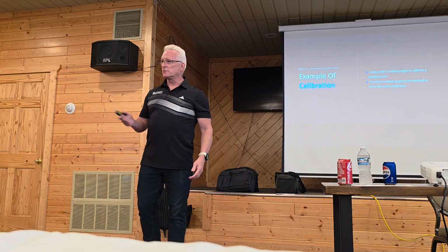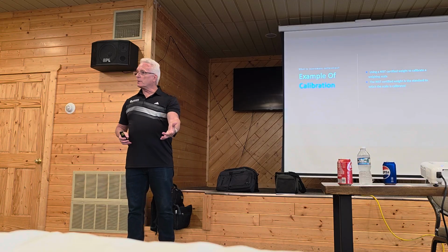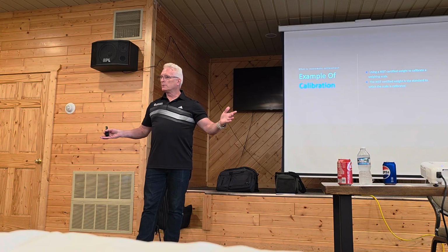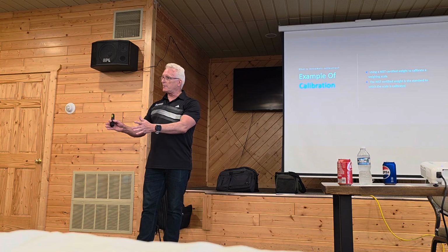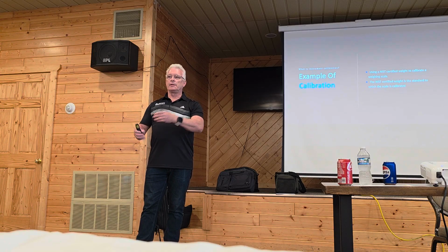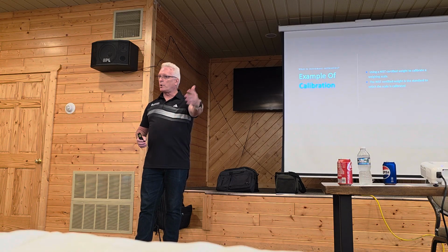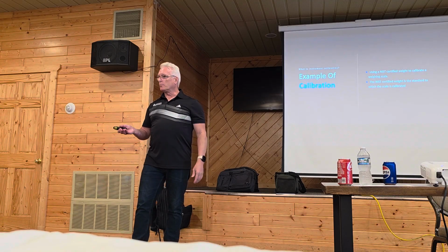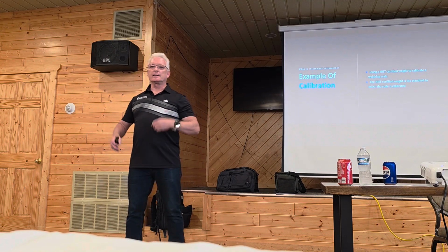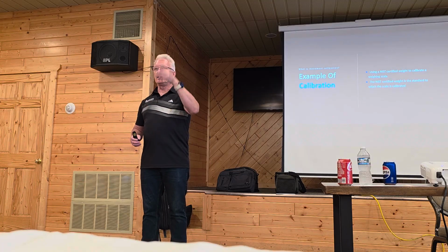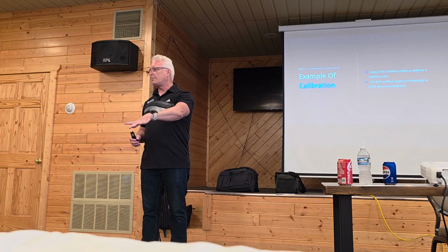So mag meters is a good example. A propeller meter, there's no verificator for it. So there's 2 ways to do that one. One is to do a clamp on and compare it, and the other way is to take it out and send it in and have measured water go through it. That's a lot of work. Take it out, send it in, it gets damaged on the way back, and blah, blah, blah. And then you don't have a meter during that time, you gotta put a cap on it.